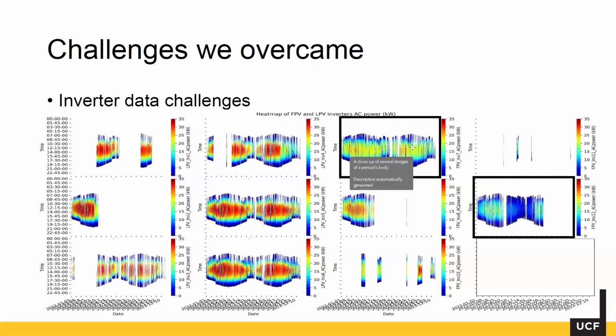So we collected the data, and we want to make sure that for those PV modules the inverter is actually running, which means we are collecting the working PV module temperature. Inverter 7 is working fine without any flaws. This inverter 7 is connected to the topmost, northwest and northeast located PV modules, so we are using those sensors.